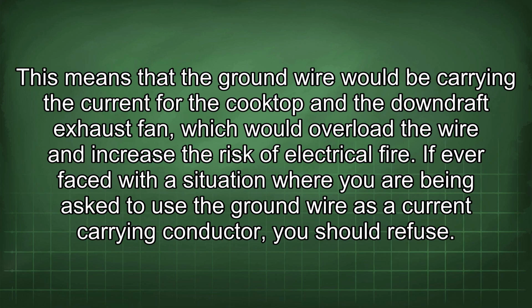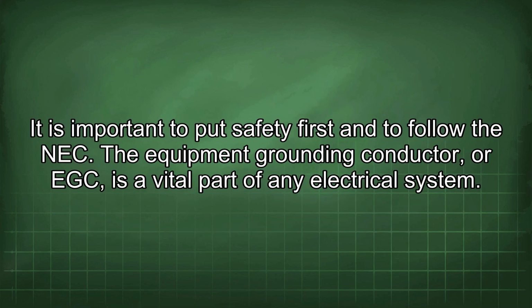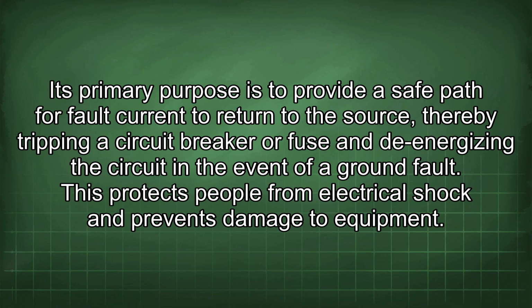If ever faced with a situation where you are being asked to use the ground wire as a current carrying conductor, you should refuse. It is important to put safety first and to follow the NEC. The equipment grounding conductor, or EGC, is a vital part of any electrical system. Its primary purpose is to provide a safe path for fault current to return to the source, thereby tripping a circuit breaker or fuse and de-energizing the circuit in the event of a ground fault. This protects people from electrical shock and prevents damage to equipment.